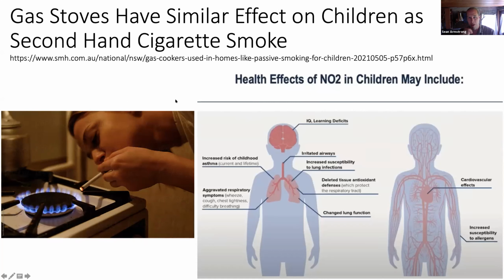So you have all the effects of secondhand cigarette smoke on children, with increased asthma rates. About 12% of asthma in children is caused by the gas stove. You see it more in smaller apartments, because they have less air volume to dilute the pollution. You might need two or three times as strong a hood in an apartment as in a house, but people don't do that - it's the reverse. Frequently hoods in apartments don't even work, and they're recirculating systems that have no effect on getting rid of nitrogen dioxide, and not much effect on PM2.5.